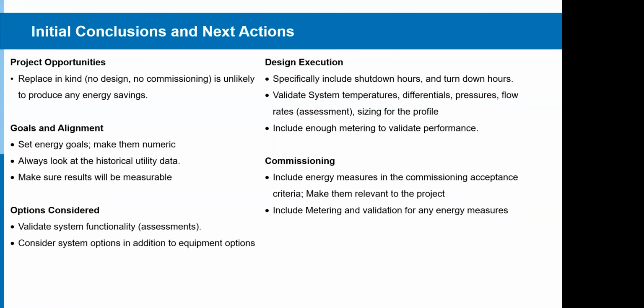In design execution, there's a whole bunch of things we try to look for: shutdown hours, turndown hours, delta T's on those water systems, flow and metering. It's very important to include enough metering to validate energy performance. If you're going to do a system that's supposed to save energy, put in the meters you need during design in order to be able to validate that.